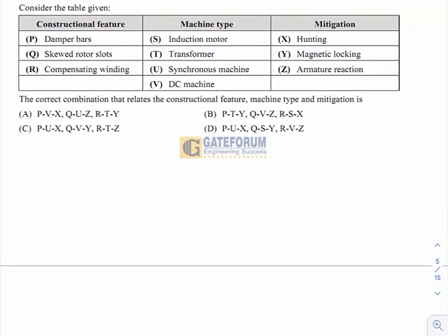That is, whenever there would be a change in load or excitation or change in the other condition of the rotor, then the synchronous motor will oscillate to and fro about an equilibrium position. So damper bar are used in synchronous motor to avoid the phenomena of hunting.